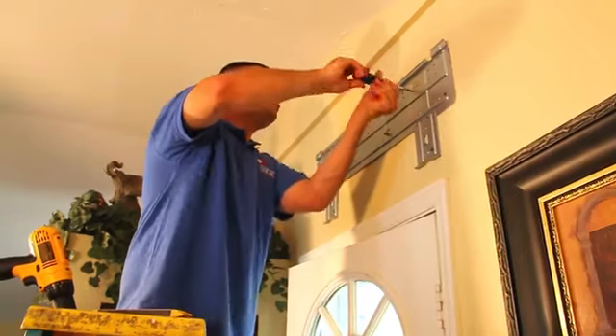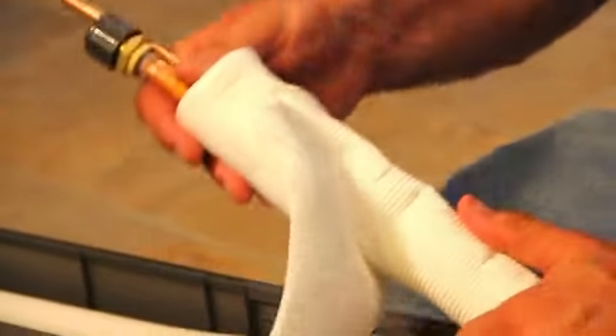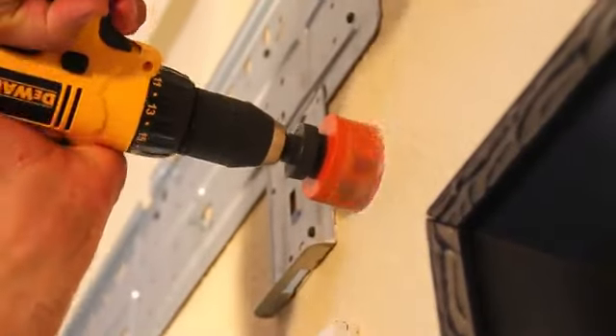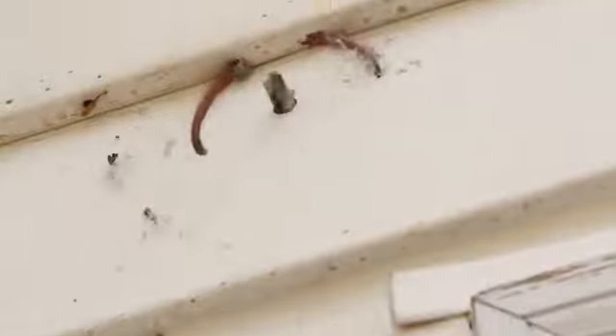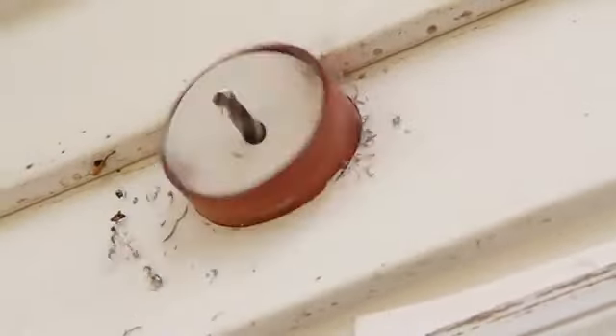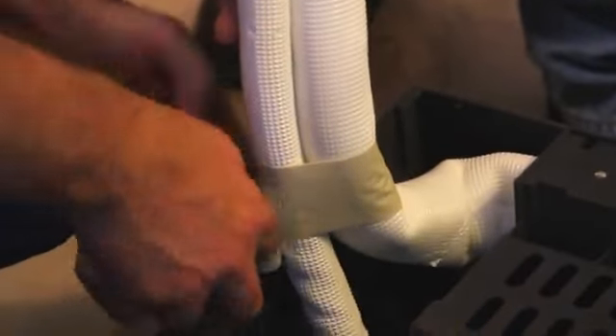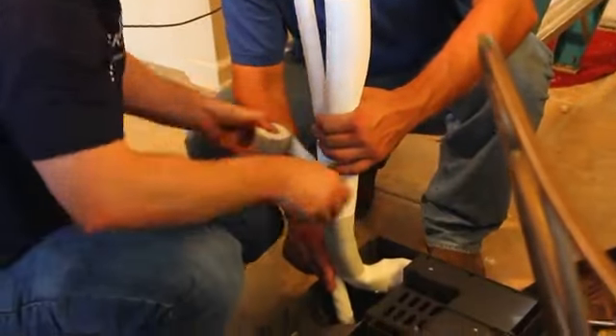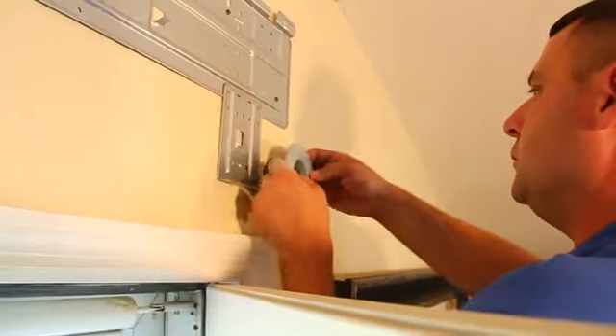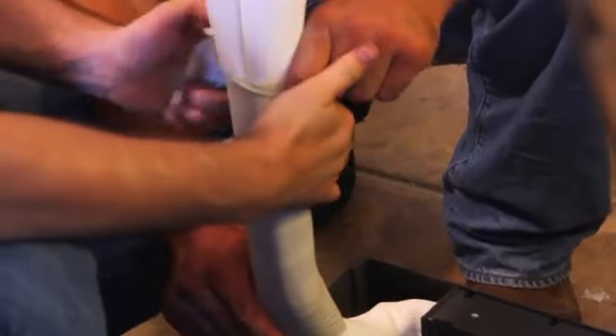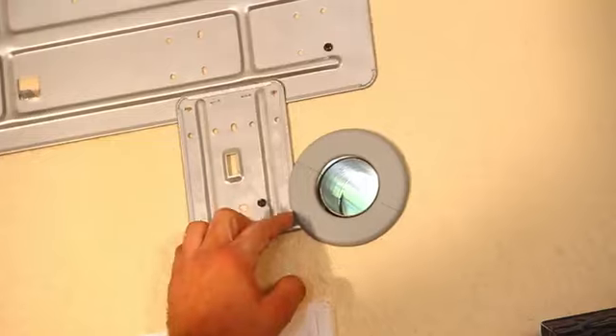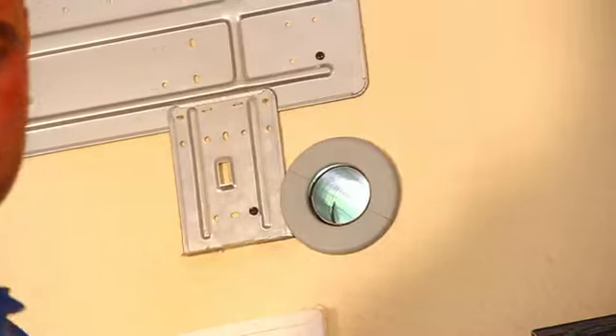Once the wall mount is ready, carefully unfold the refrigerant pipe, making sure not to damage the tube in the process. Next, drill the hole for condensate drainage, making sure to angle the hole slightly downward so gravity can do its job. It is important to note that you are going to combine the condensate tube, refrigerant line, and conduit wire in the same bundle, so you only have to have one hole going through your wall. Secure these together using tape, and make sure the bundle is tightly packed to reduce needed space, and making running them through the wall easier. Be careful not to damage the components in this process.